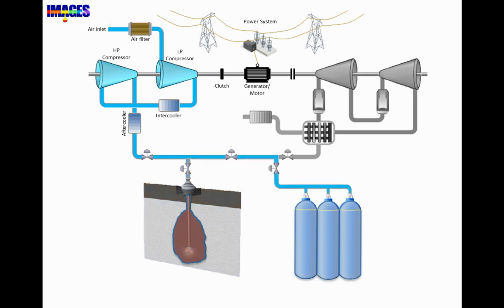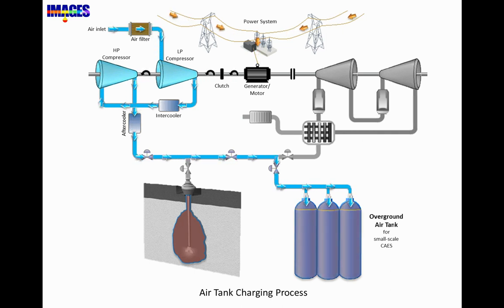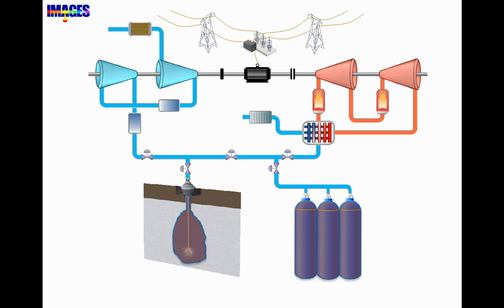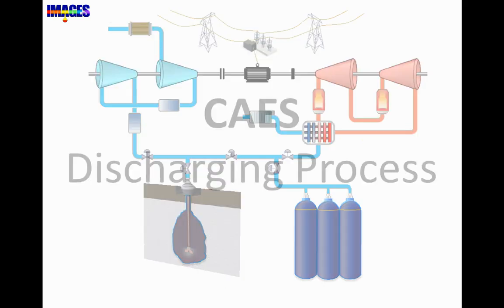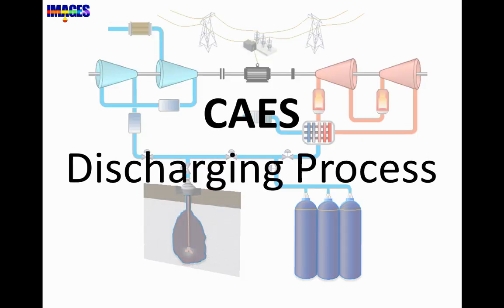For small-scale systems, an overground air tank can be used. The compression process normally uses inter-coolers and after-coolers to reduce the working temperature of the injected air, thus improving the compression efficiency and minimizing thermal stress on the system component walls. The pressure of compressed air in an overground tank is up to 300 bar.